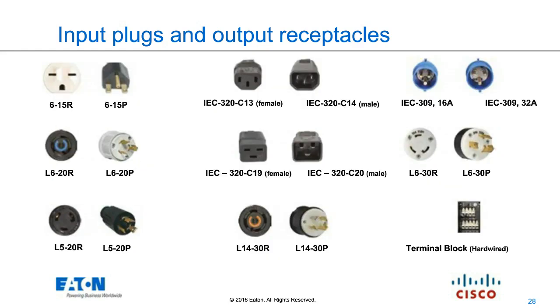So, and then to take it just a little bit further, here's the larger gamut of receptacles, and this still is not inclusive. But now we're starting to get out of the realm of just the 120 volt and more into what we can do with 208 volt, which again is going to play back into that density. Ohm's law is going to tell us that if I can increase the voltage, I can decrease current needed. And when it comes to conductor sizing, ultimately what's going to dictate the limit of that circuit is the diameter of the copper that the electrician ran from the breaker to the receptacle. So if we can increase the voltage on that circuit, then we can decrease the demand for current and get the customer the wattage that they actually needed.